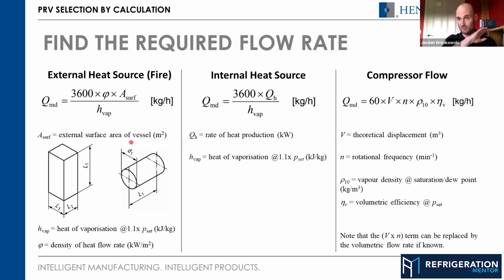The standard does say you always use all of them, or as many as are applicable, and then pick the worst one. But you can usually tell, and most of the time it's the external heat source that people use. Again, as I said, except for what we typically see on transcritical CO2 systems, where people use PRVs on discharge lines, and then it's obviously the compressor, because it's not even connected to the receiver; it's coming straight from the compressor. That's right. Yeah.